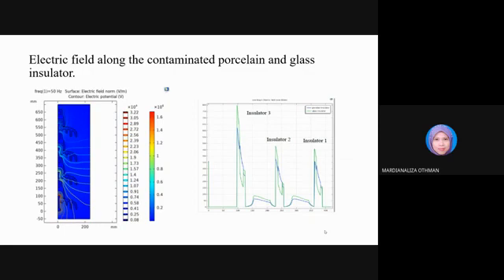Now we move to the result of the electric field along the contaminated porcelain and glass insulator. In this section, a thin layer of contamination is added on the 4-unit ceramic insulator surface to investigate the effect of contamination on the electric field distribution of the insulator string.